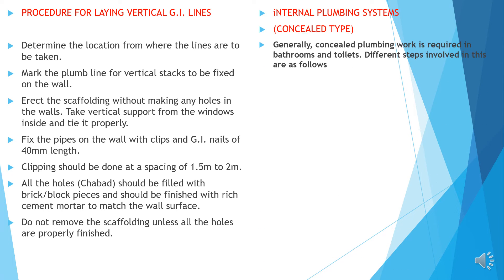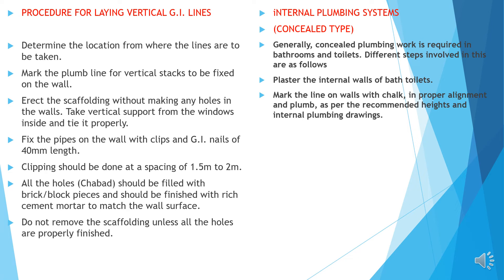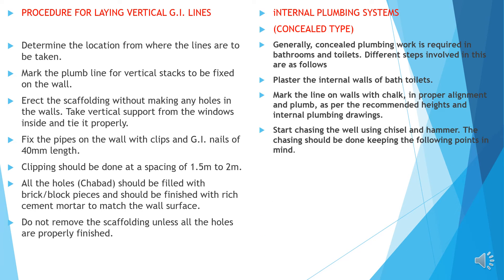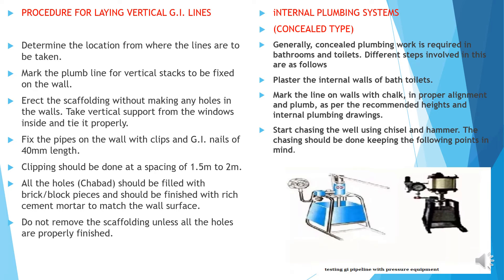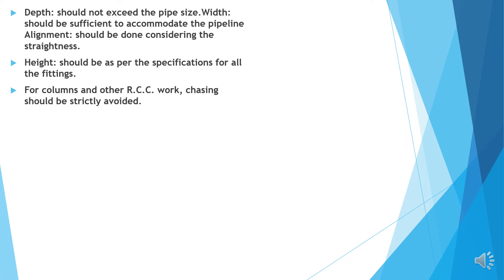Internal plumbing system — concealed type. Generally concealed plumbing is required in bathrooms and toilets. Different steps involved: plaster the interior of both toilets. Make lines on walls with chalk in proper alignment and plumb as per recommended heights and internal plumbing drawings. Start chasing the wall using a chisel and hammer. The chasing should be done keeping the following points in mind. Depth should not exceed the pipe size but should be sufficient to accommodate the pipeline. Alignment should be done considering the straightness. Height should be as per specifications. For columns and other structural members, chasing should be strictly avoided.